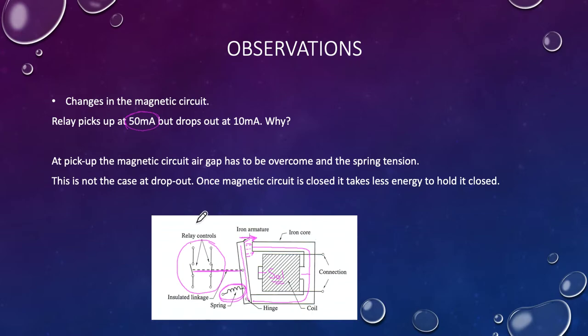But this is not the case at dropout. Once the magnetic circuit is closed, it takes less energy to keep it or hold it closed. So once I've got it closed, it doesn't take anywhere near as much energy to hold it closed. That's why at dropout it only takes 10 milliamps. I can drop the current all the way from 110 milliamps at 24 volts.